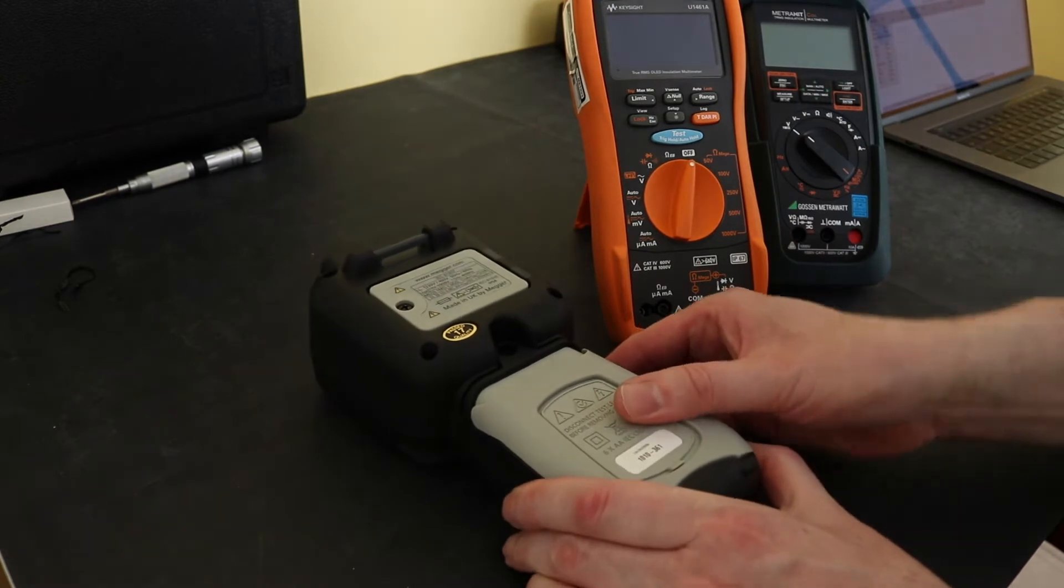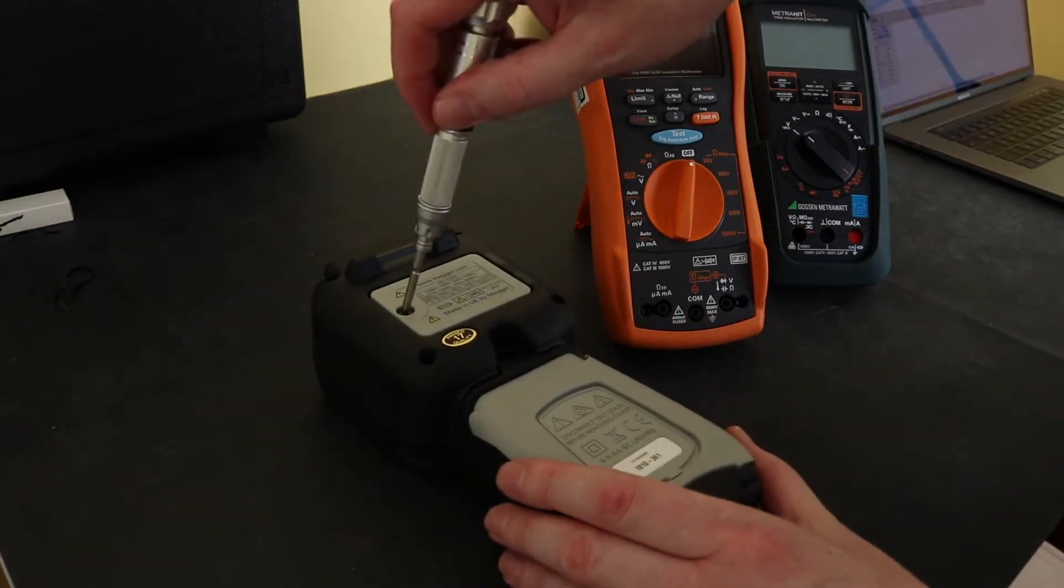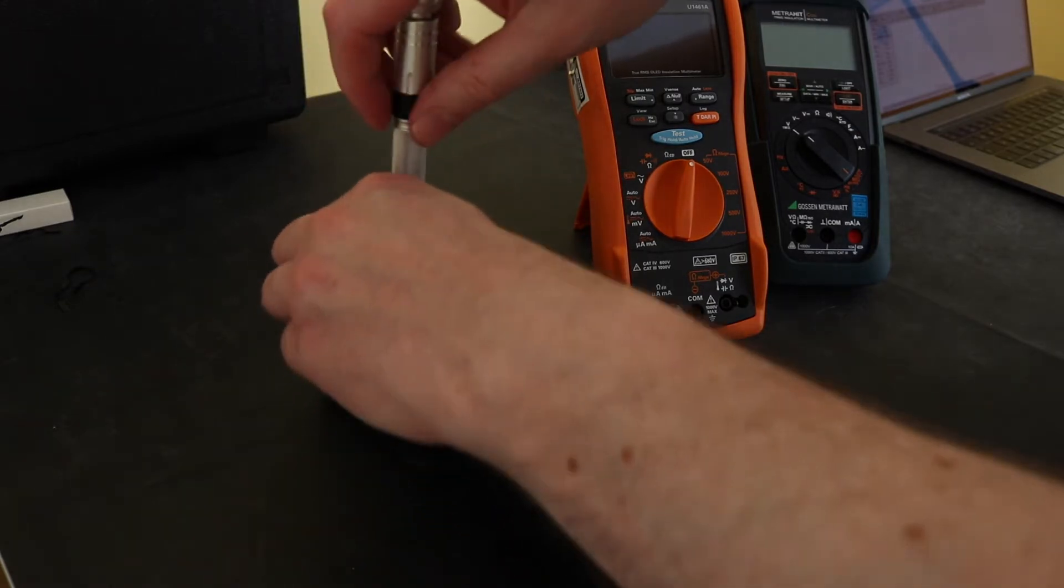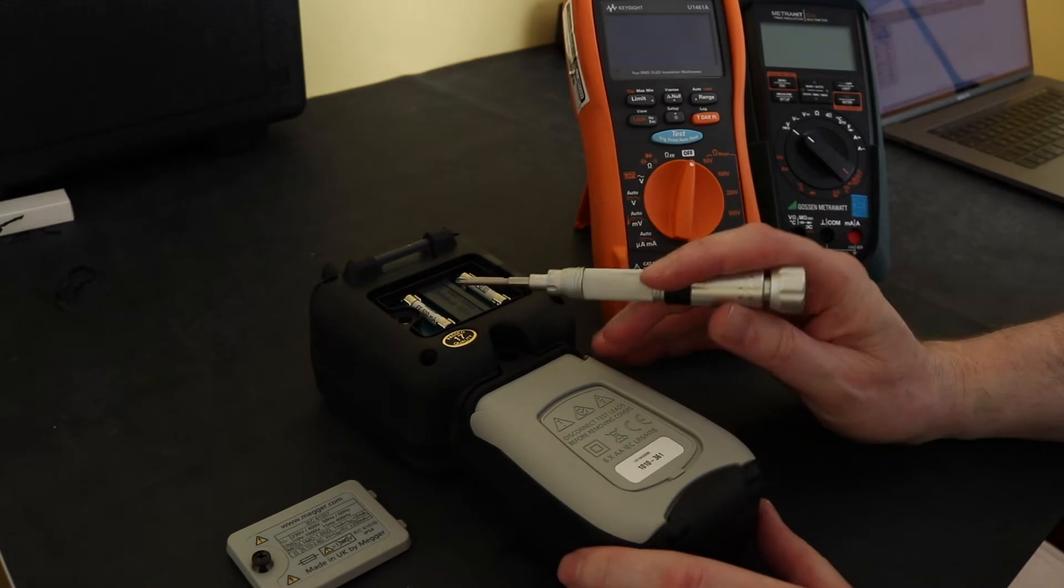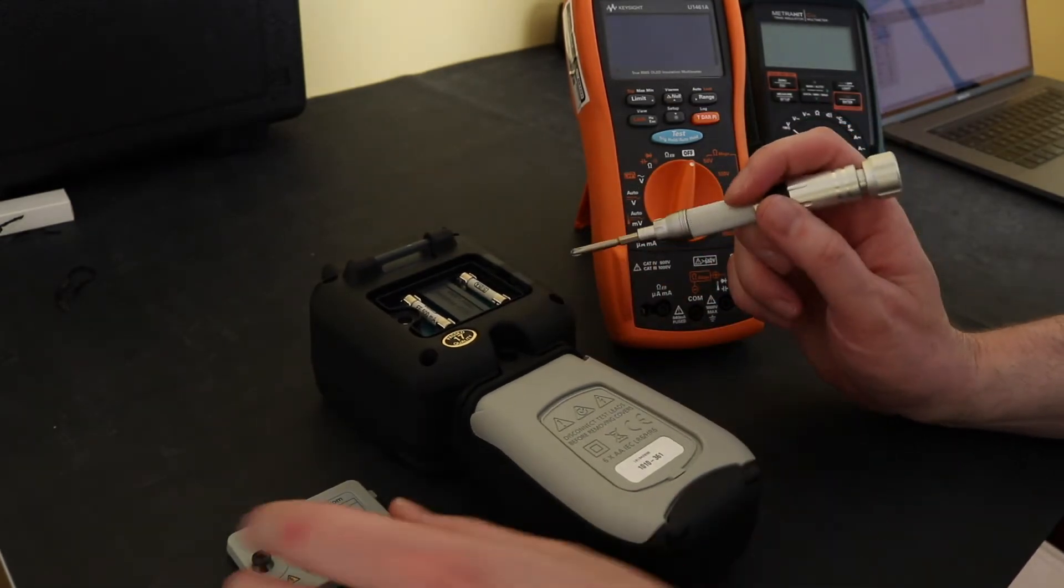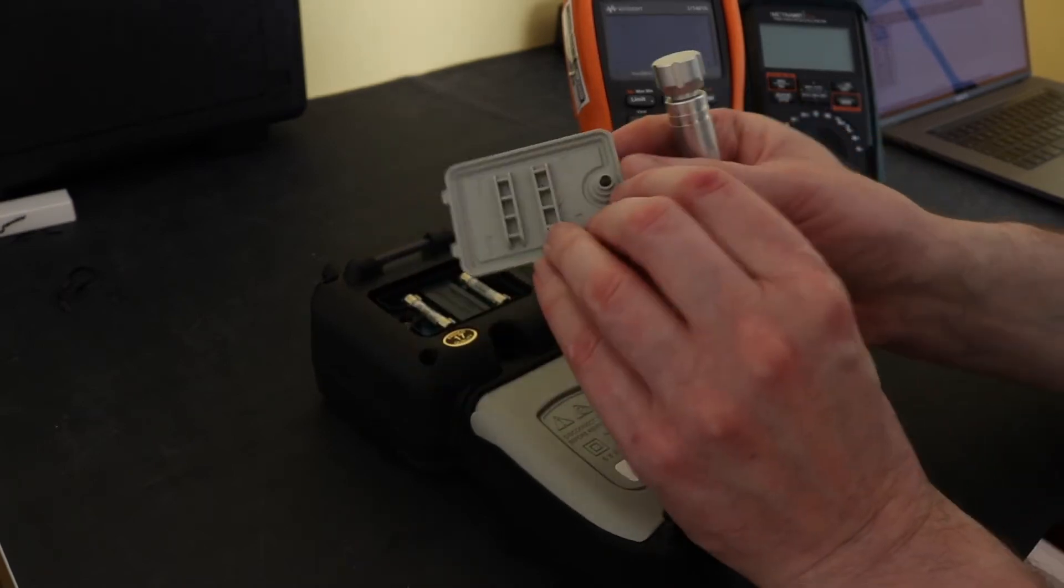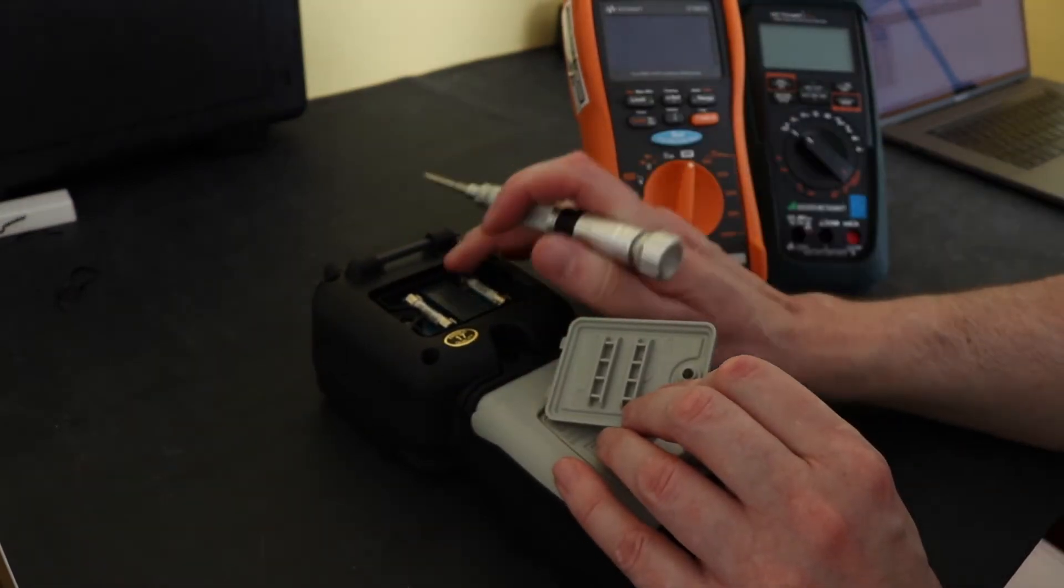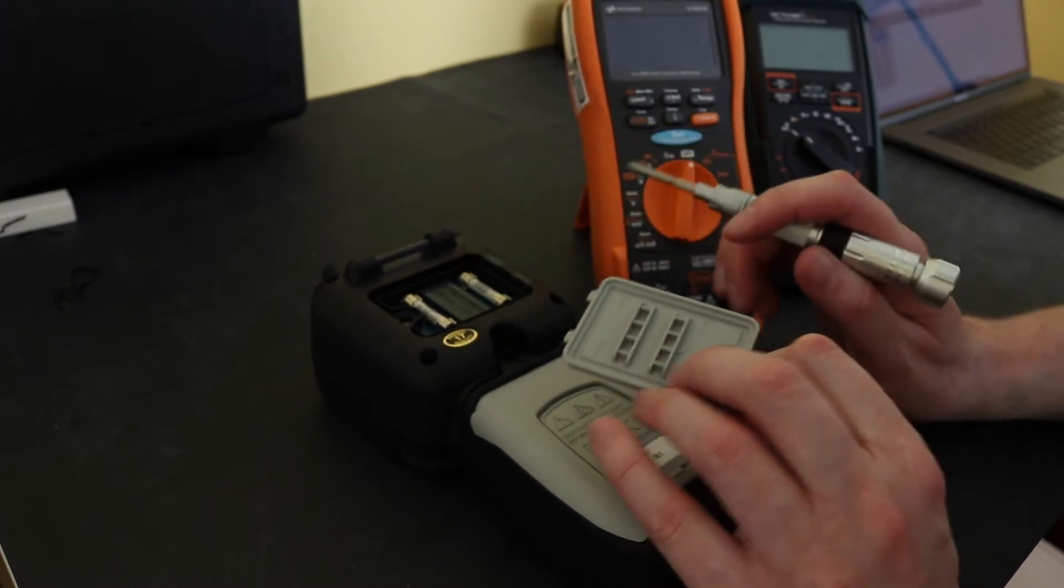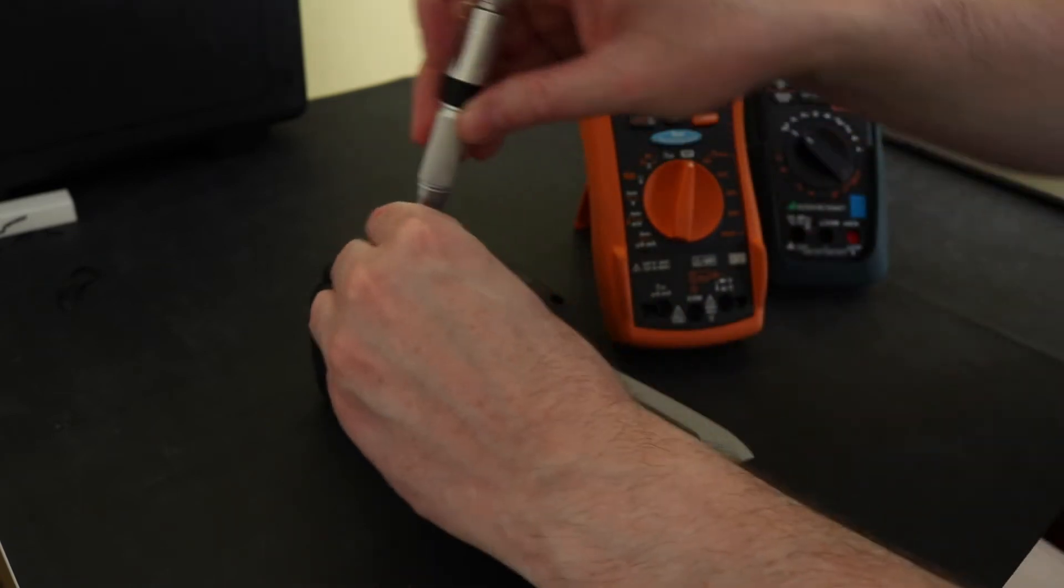For this actual MTR-105 you can see I have immediate access to both the fuse compartment. There you have a fuse here for live terminal and another fuse for the guard terminal. These are captivated screws and this section of the lid is actually rubberized so you've got a seal there for any moisture and dirt ingress.